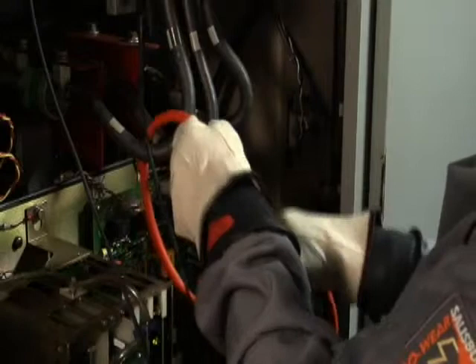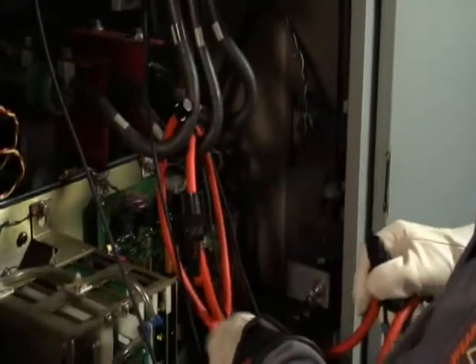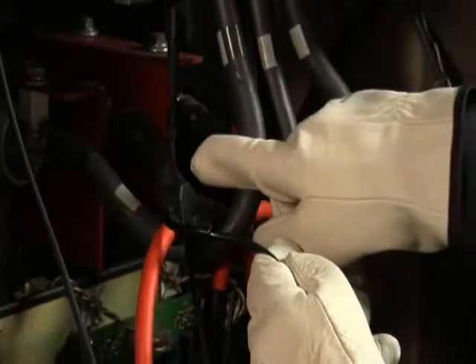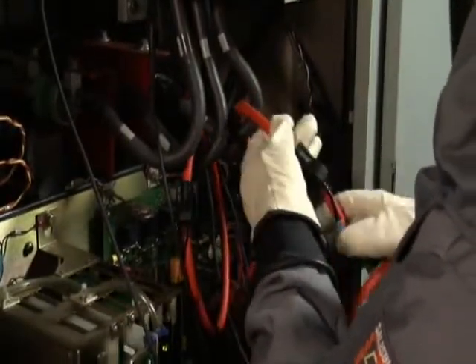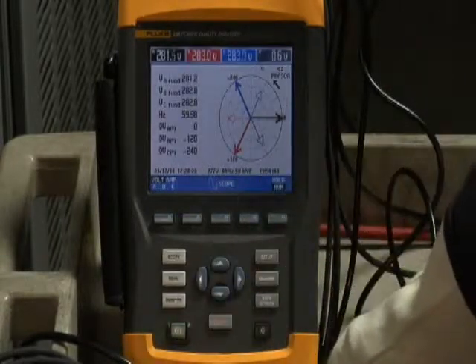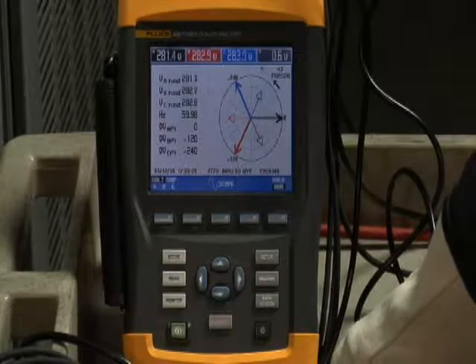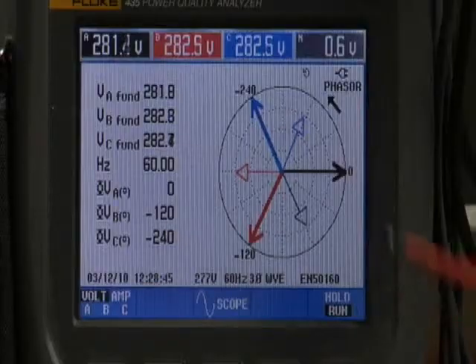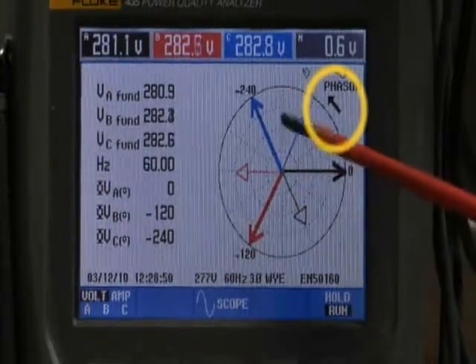Probes on the wrong phase. If you have a phasor rotation problem, take a look at your connections. Go back to the current clamp and the voltage leads and make sure that their color coding matches up. If they are mismatched, swap the leads as necessary to correct the problem. Then always go back to your power quality analyzer's phasor diagram and make sure that for A, B, C rotation, the arrow is pointing in a counterclockwise direction.